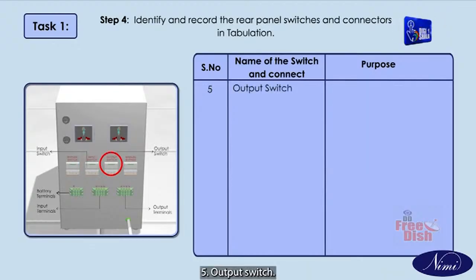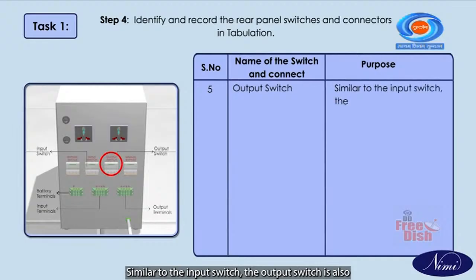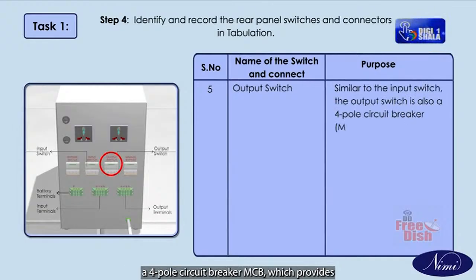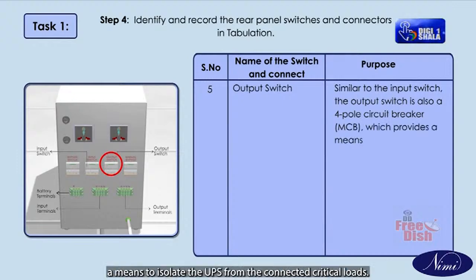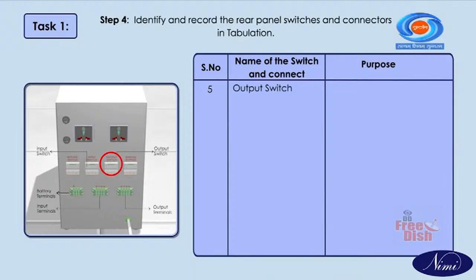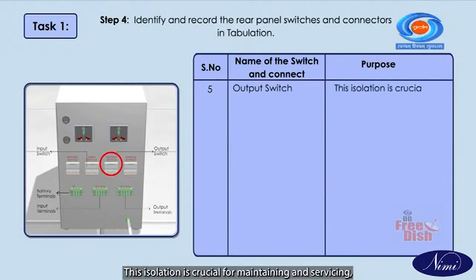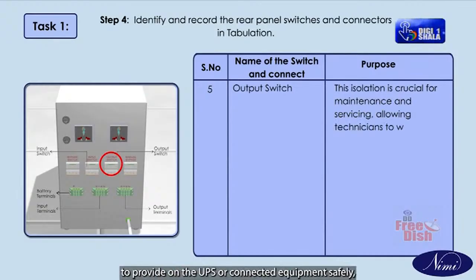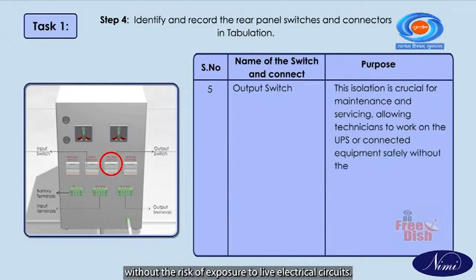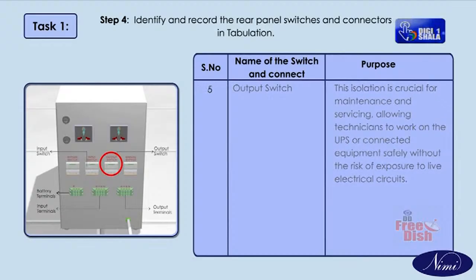Number 5. Output switch. Similar to the input switch, the output switch is also a 4-pole circuit breaker MCB, which provides a means to isolate the UPS from the connected critical loads. This isolation is crucial for maintenance and servicing, allowing technicians to work on the UPS or connected equipment safely without the risk of exposure to live electrical circuits.